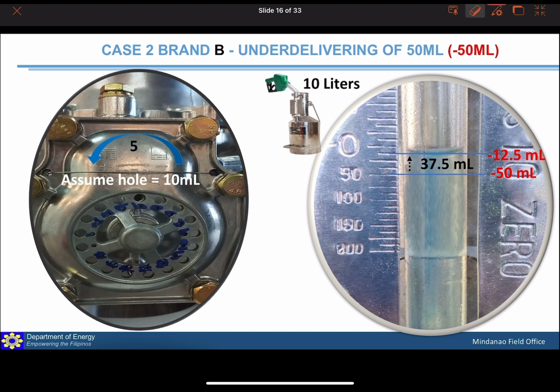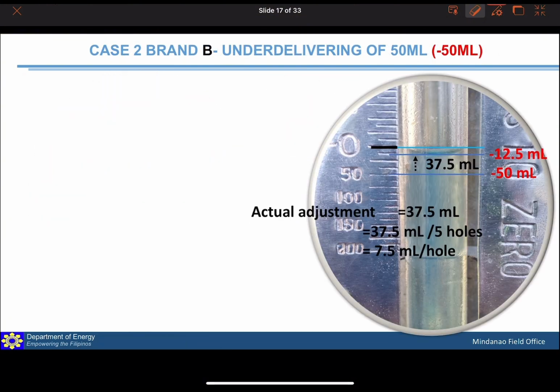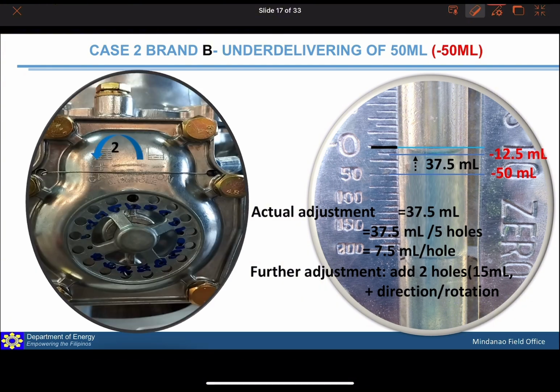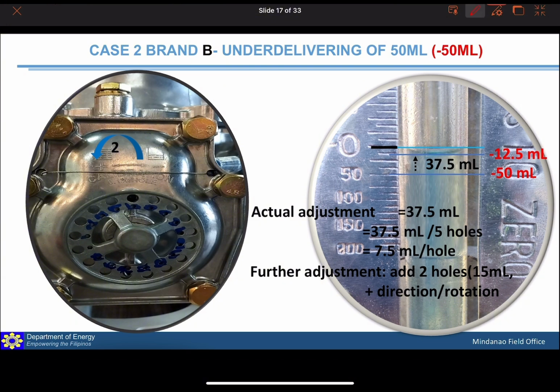The actual change or the actual adjustment is 37.5 lang. Kasi minus 50 minus 12.5 ml is 37.5 ml. Therefore, 37.5 ml divided by 5 holes, ang value per hole is 7.5 ml. So, may kulang pa na 12.5 ml. For further adjustments, kasi sabi, based on our trial and error, ang hole daw is 7.5 ml per hole. So, we need to add 2 holes, which is 15 ml. An additional of 2 holes para ibalik ang calibration into 0. Here.